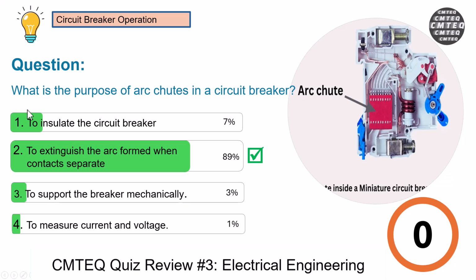Now, obviously options 1, 3, and 4 are not correct. Insulation is provided by a different material, not the arc chute. It's not to provide mechanical support, because that's provided by the frame of the breaker. And it's not to measure the voltage and current, that is done by the CT and voltage transformer at the point of connection.